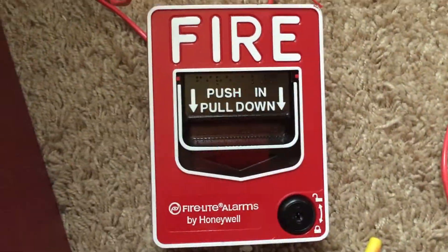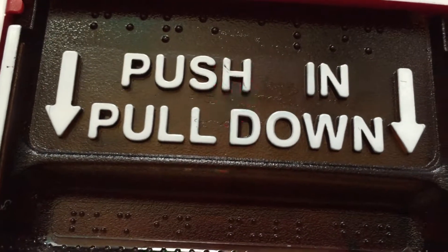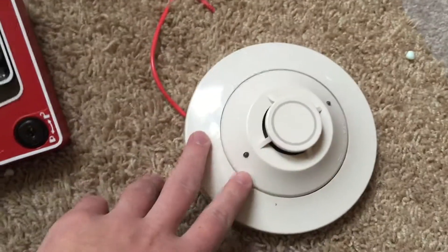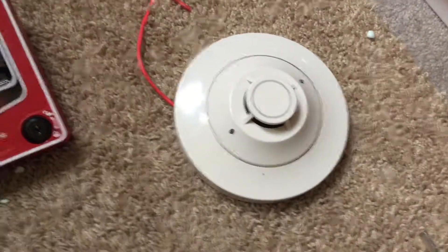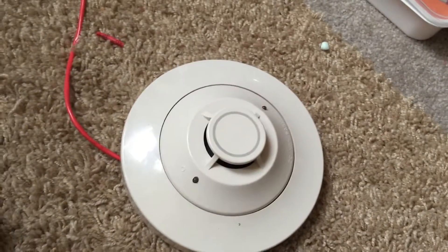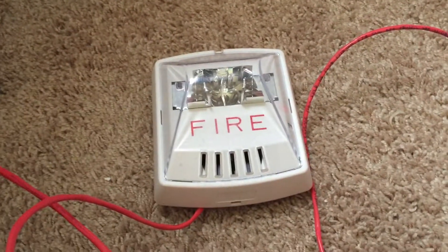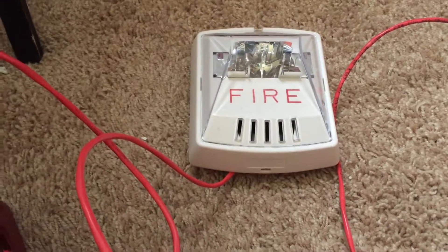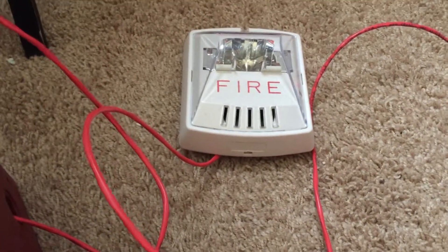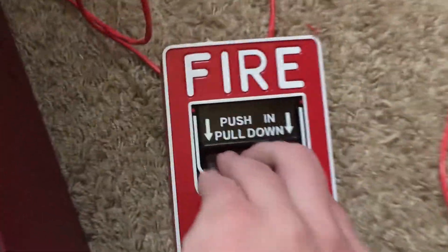Moving on to the devices — here's a Fire-Lite BG-12LX. You can see the blinking light right there, indicating that it's communicating with the panel. Along with that, on the same loop actually, we have this Fire-Lite heat detector — I forget the specific model number of it, but you can see the LEDs on this flashing. And then for an alarm, I have this white Wheelock Exceder hooked up, set to code 3, and two-wire silence is enabled on this. So I think I'll go ahead and pull the BG12LX now — here we go.